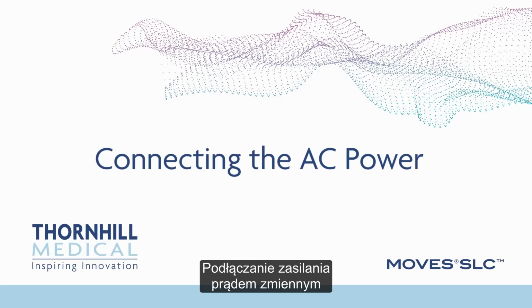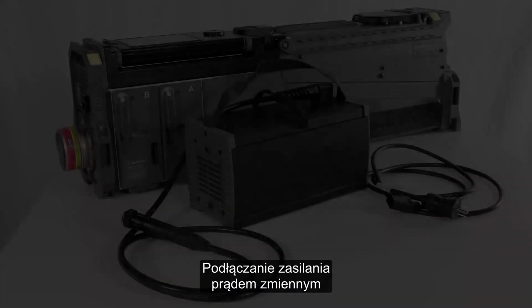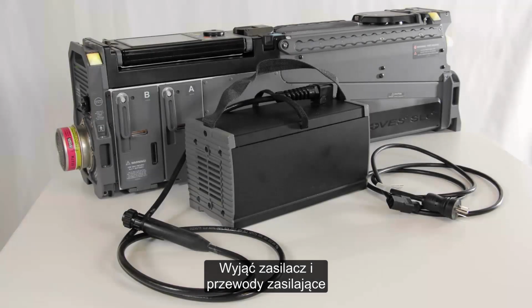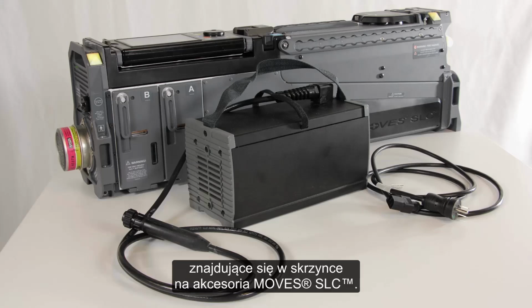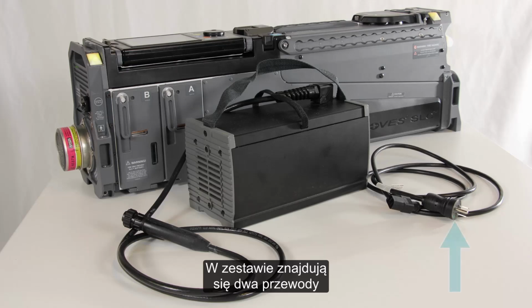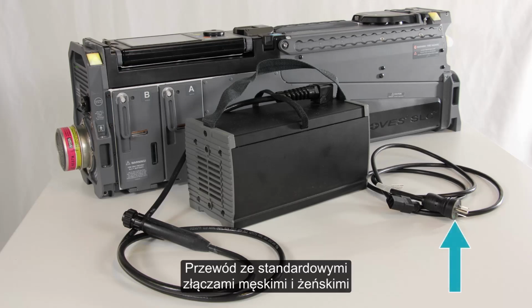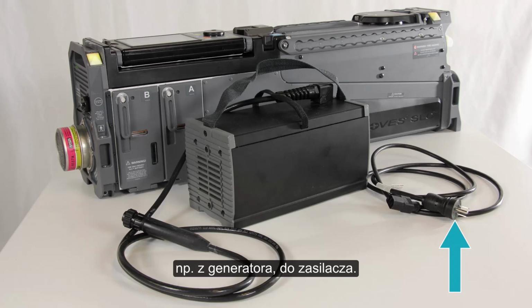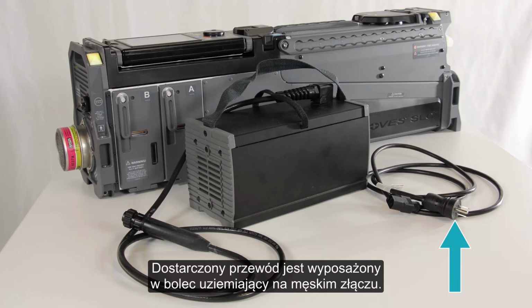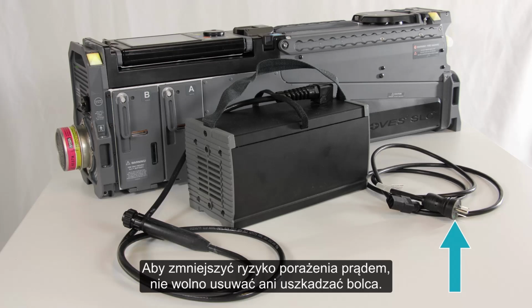Connecting the AC power. Remove the power supply and power supply cords that are stored in the Moves SLC accessory case. There are two cords supplied. A cord with a standard male and female connector supplies the power from a wall socket or line supply, such as a generator, to the power supply. This cord is supplied with a grounding prong on the male connector. To reduce the risk of electrical shock, this prong should never be removed or compromised.